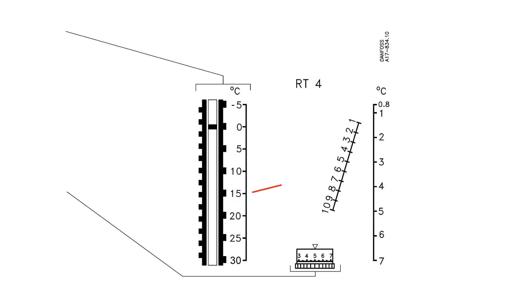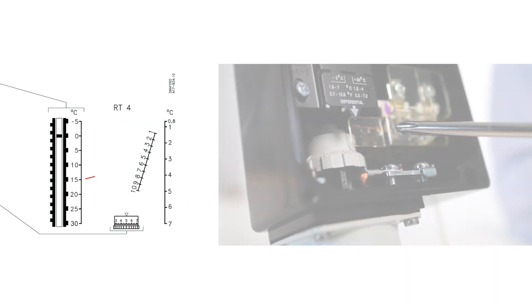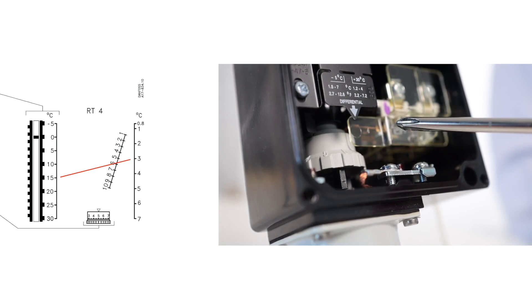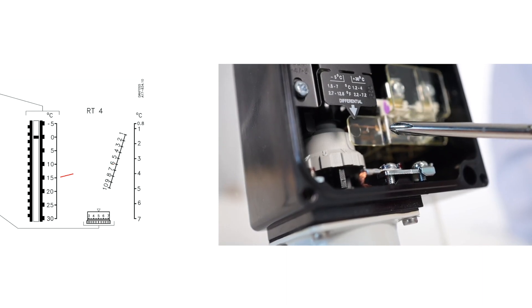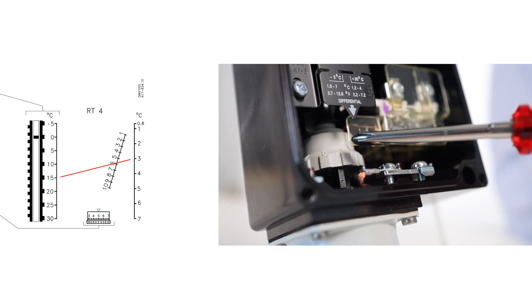In the instructions, you can find the table that shows which differential level corresponds to each setting level. If you, for example, need a differential temperature level of 3 degrees Celsius, you should adjust the setting to 6 with the setting nut.